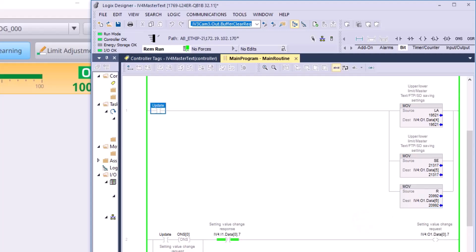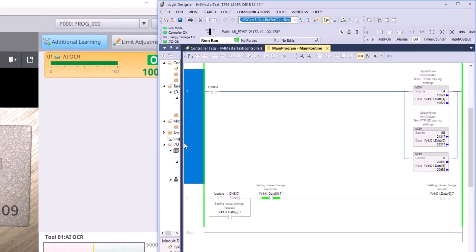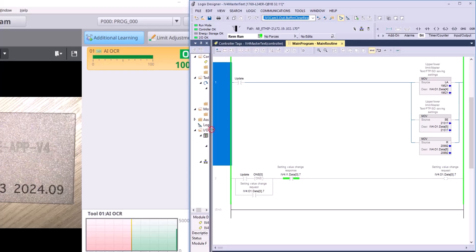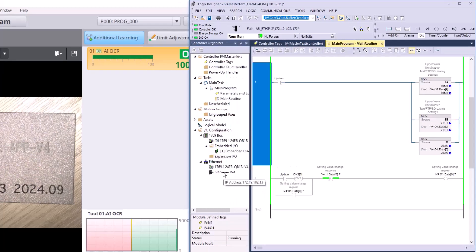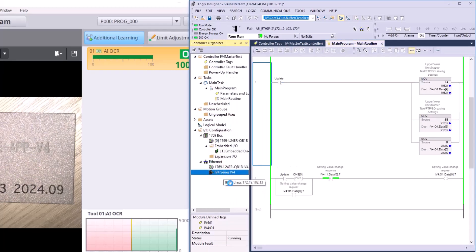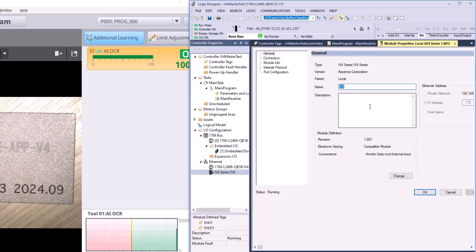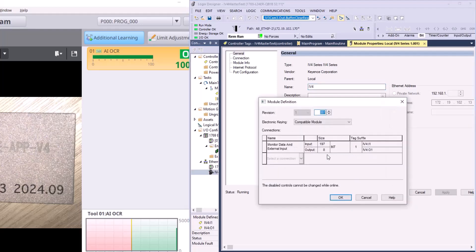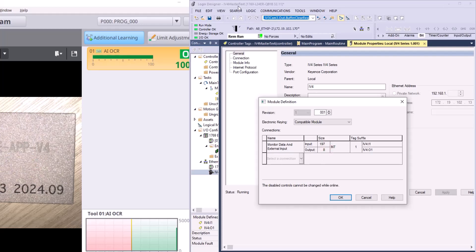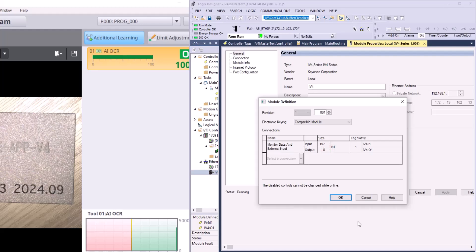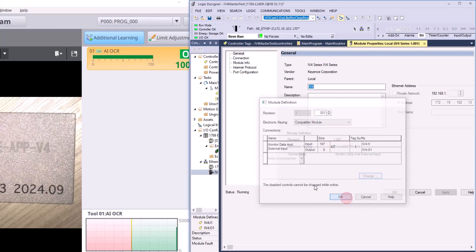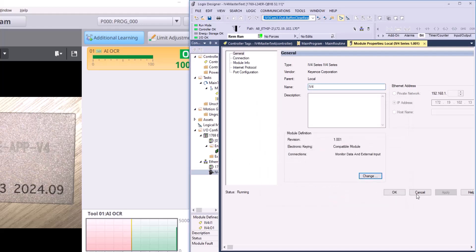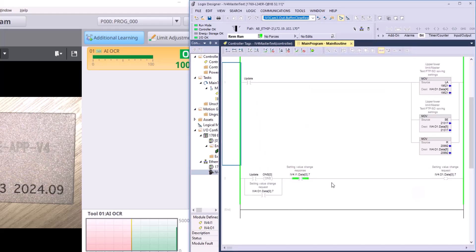When you first load in the IV4 by default, I'm going to pull this up here, show you the properties, the size of it may not be large enough on the outputs for you to get all of those in there. So, I've set mine to 8 so we have enough room to send all these characters. You can just go in here when you're offline and increase the output size of the module. However many characters you need to send, you may need to increase it a little bit there.